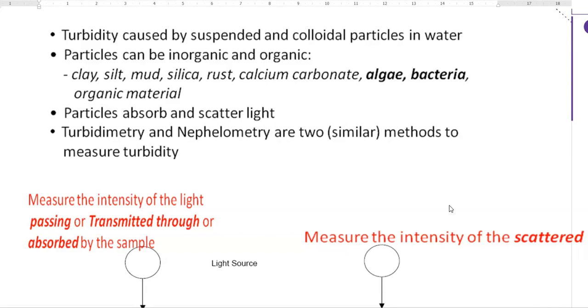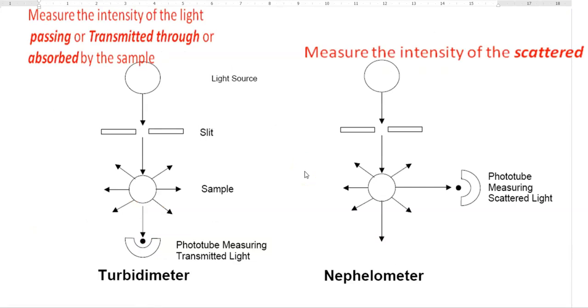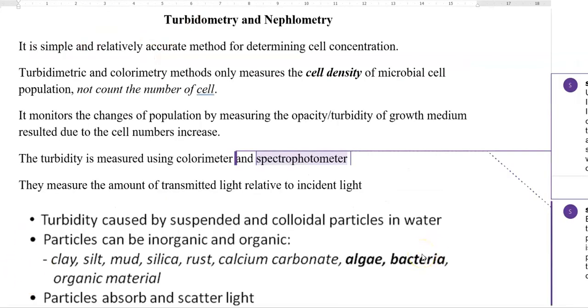Turbidometry and nephelometry are two similar methods used to measure turbidity. A turbidometer is an instrument that measures the intensity of light passing or transmitted through or absorbed by the sample. This is a line diagram showing the various parts of a turbidometer, where a light source is present, where a sample is kept, and how a phototube measures the transmitted light. The principle of turbidometry is applicable with two instruments: colorimeter and spectrophotometer, which measure the amount of transmitted light relative to incident light.